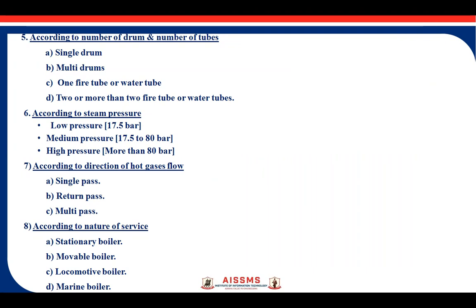To make a large amount of steam for different industrial applications, we can go for single drum or multi-drum configurations. For pressure classification, low pressure boilers create up to 17.5 bar, medium pressure boilers up to 80 bar, and high pressure boilers create pressure greater than 80 bar.